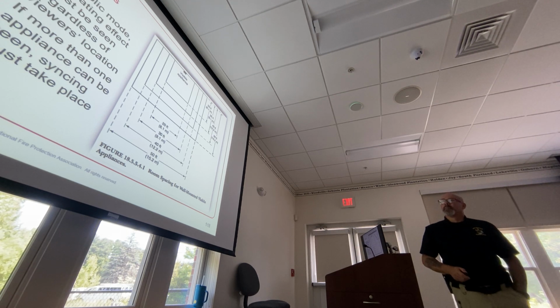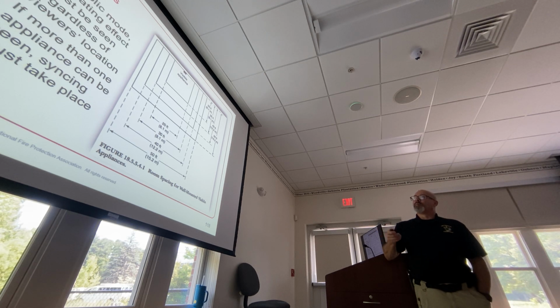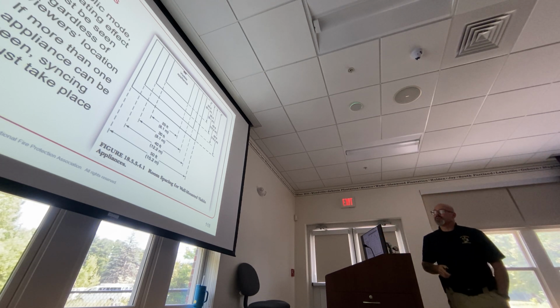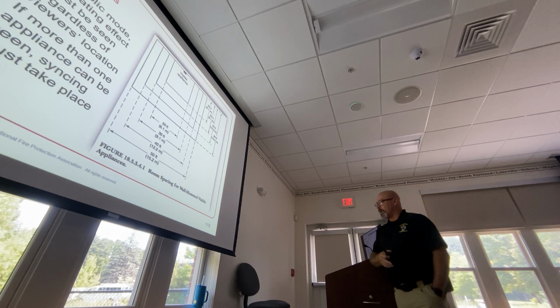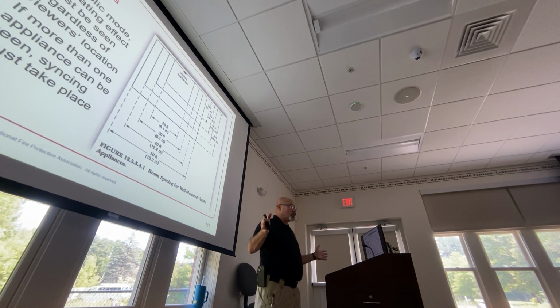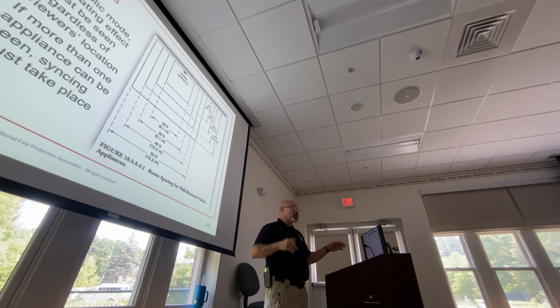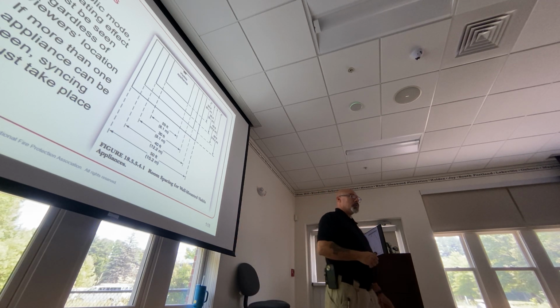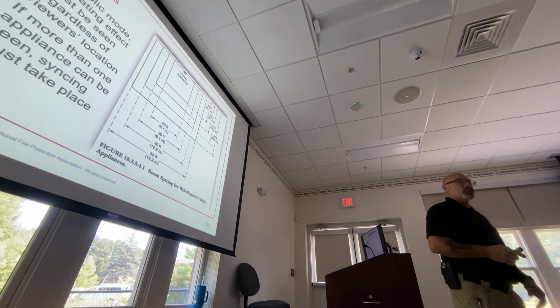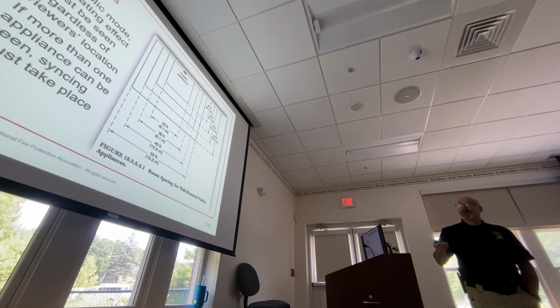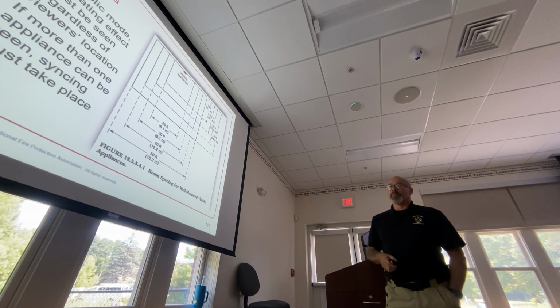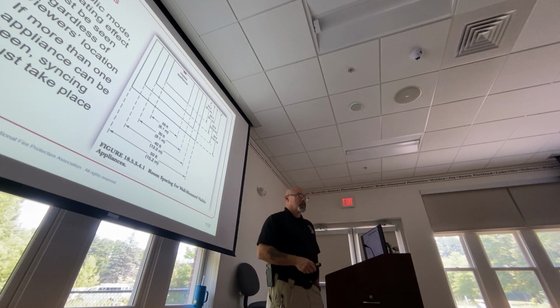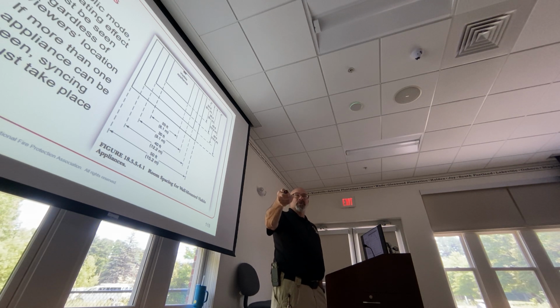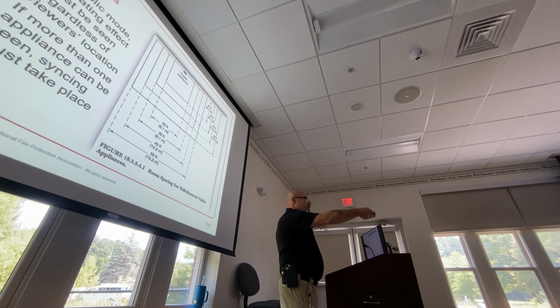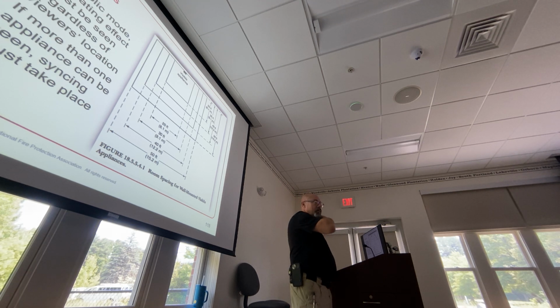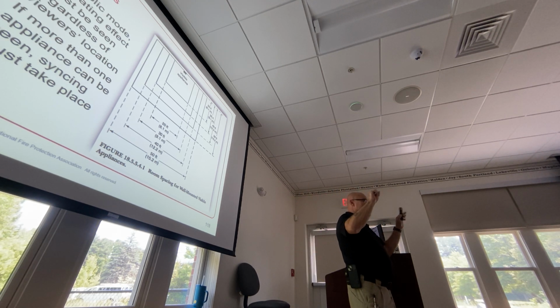Okay? Public mode operating effect must be seen regardless of the viewer's location. In a public mode, wherever I am in this 50 by 50 room or 40 by 50 room, I should be able to see a visual appliance notifying me. There should be a strobe there. If more than one appliance can be seen, syncing must take place. What does that mean? I'm standing here, I have a visual there, a visual back there, and a visual right here. They all have to go off at the same time, they all have to strobe at the same time. And why?